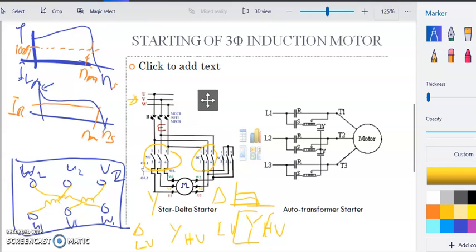Okay. Another kind of control, how to control the starting current, is by introducing resistance and impedance to the circuit that goes into your motor. It was stated inside your notes that another way to reduce the starting current is to insert extra inductors or resistors on the power line of the circuit during starting. Then once it runs, we just remove the resistor and continue with the normal lines, or we use an auto transformer starter to reduce the incoming voltage.